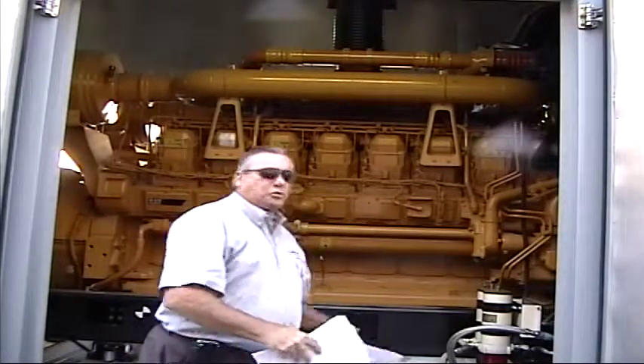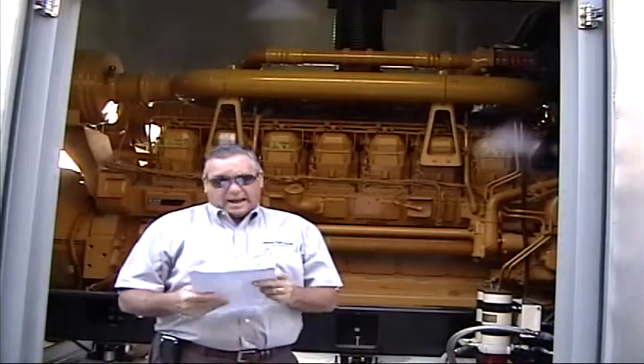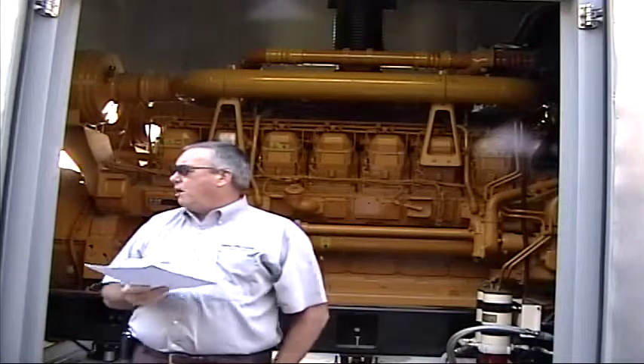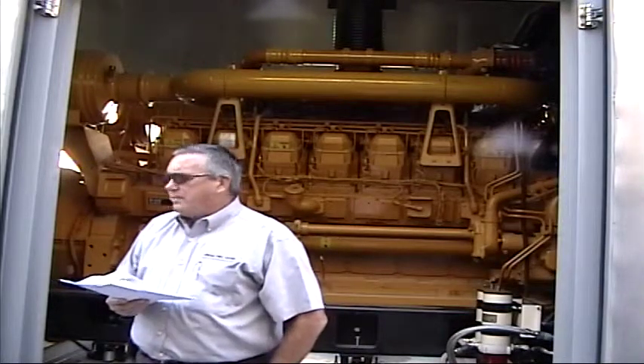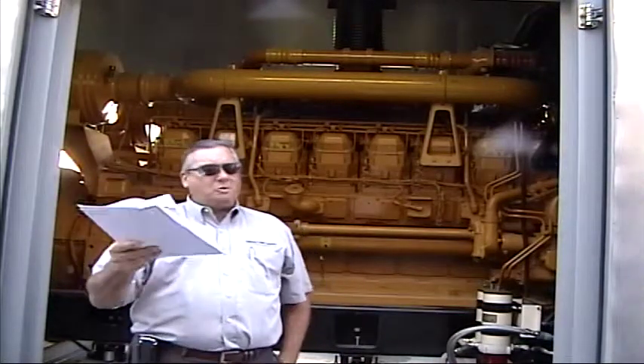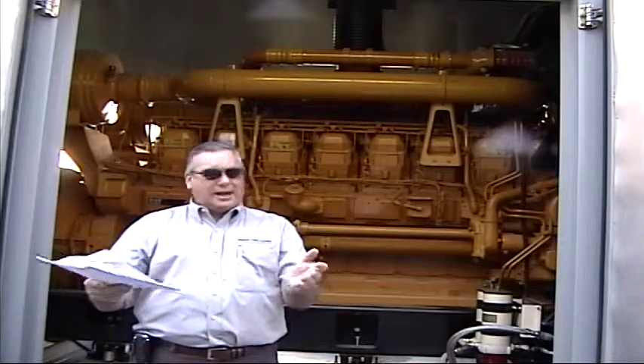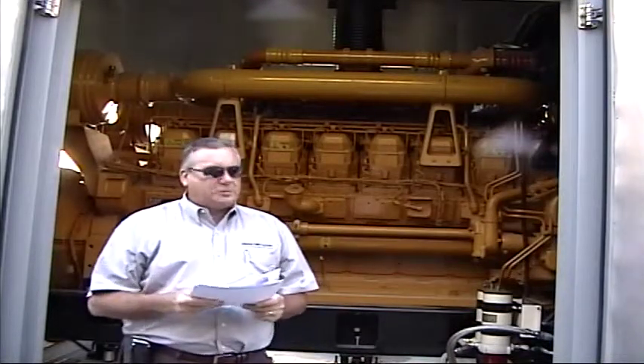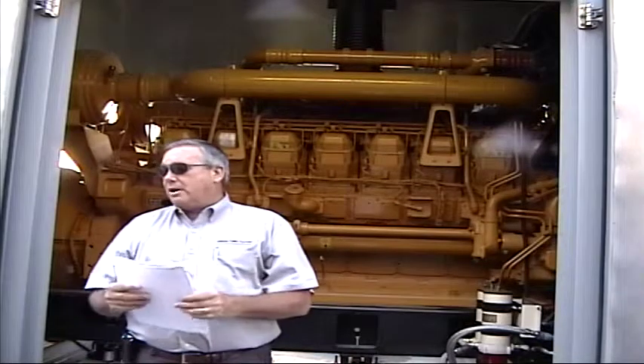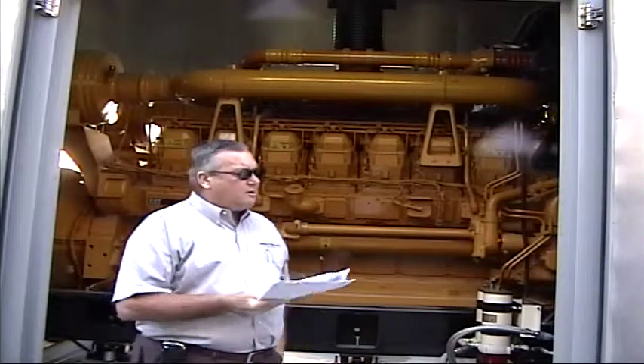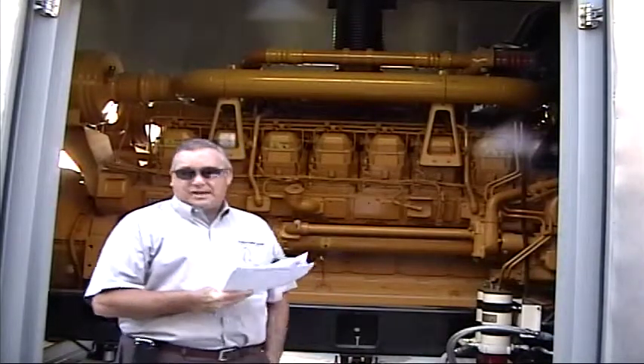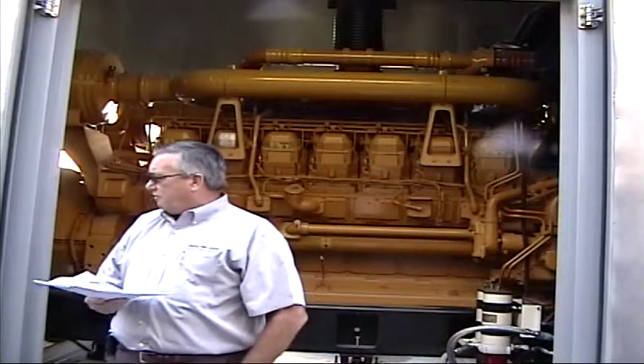The fuel tank's 1,200 gallons, and I did a calculation based on load. At 100% load, you're about 138, 139 gallons an hour, so you have 8+ hours of fuel.